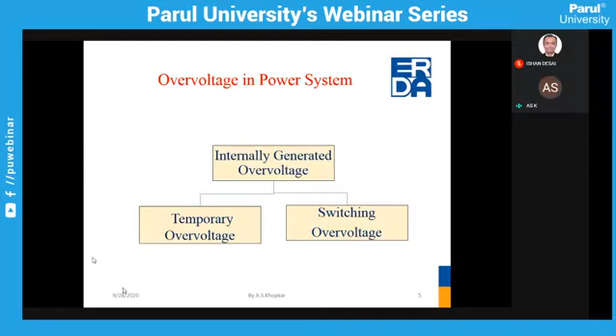So basically the over voltages in the power system are divided into two categories. We'll see how the internally generated over voltages are again divided into two parts: the temporary over voltage, and the switching over voltage. Temporary over voltages last maybe for a few seconds, like 30-40 seconds, and they occur when we suddenly switch on or switch off a light load. On the other hand, switching over voltage means whenever there is a heavy load and we suddenly switch it on or off, such over voltages are generated in the power system. These are called switching over voltages. They may last for milliseconds, but they will appear in the power system.